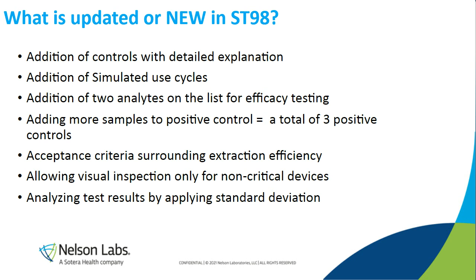Now, for controls and validation, I'm sure if you have been working with reusable devices, you are aware of these controls and have been testing them since 2015 when the FDA guidance document came out. They did list all these controls in there, but it was only in the FDA guidance document. And when it's a guidance document, it's not something that you have to do, but it is a recommended practice that you should consider. And because it was considered in that manner, it made sense to add it to a standard that talks about cleaning validations for these devices. So they were actually taken out of the FDA guidance document and imported into this standard.